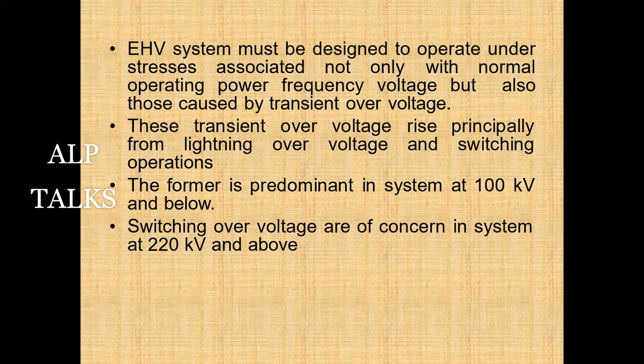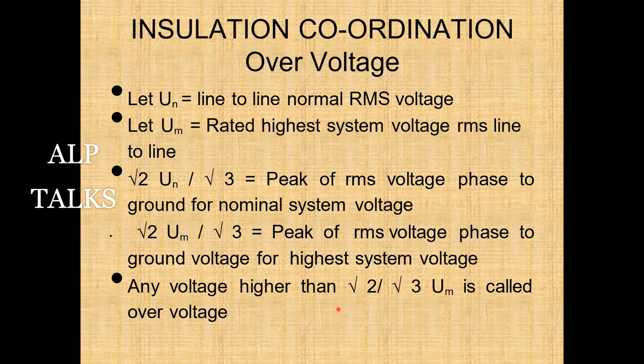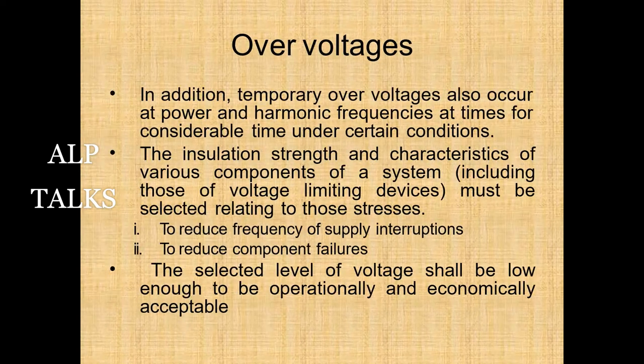In insulation coordination, Un is line-to-line normal RMS voltage and Um is the highest system voltage line-to-line. The peak ground voltage is √2/√3 × Um. Any voltage higher than this peak value is called an overvoltage. Temporary overvoltages also occur at power and harmonic frequencies for considerable time under certain conditions.